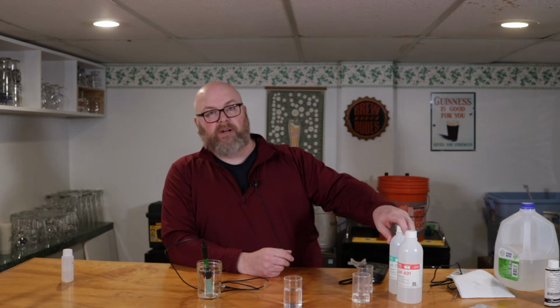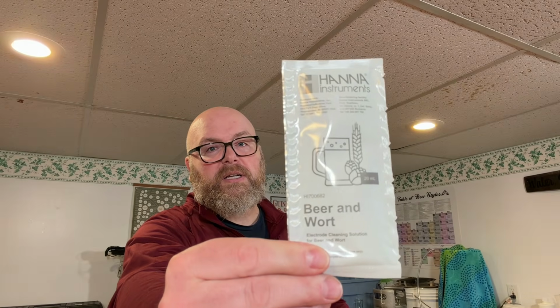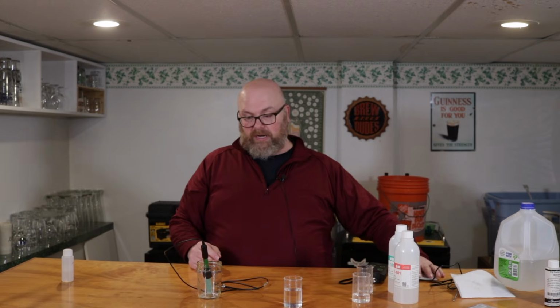If your probe won't calibrate, or you think you're getting really bad readings, it's probably time to get a new probe. But as long as you take care of it, rinse it really well in a non-electrolyte solution like distilled water. Use your storage solution. That should be really good. They make these sort of beer and wort cleaning solutions where you just soak the probe in one of these for a little while too, so that's good. I haven't had to do that yet. I feel like it's pretty good because the protein and stuff gunks up the probe. The probe is actually fairly porous. That's how the ions are moving back and forth. So that's how you calibrate your probe for the Milwaukee MW102 pH meter.